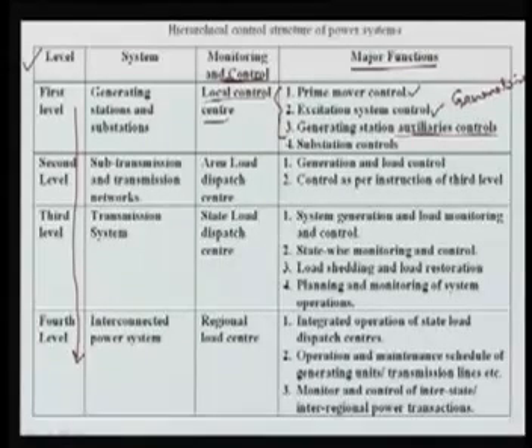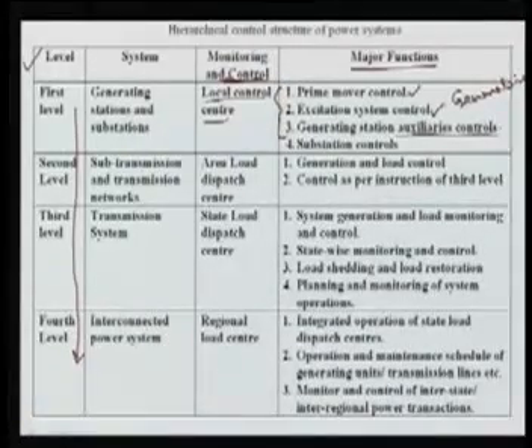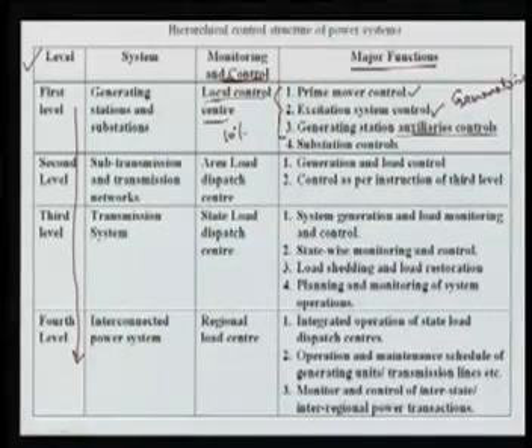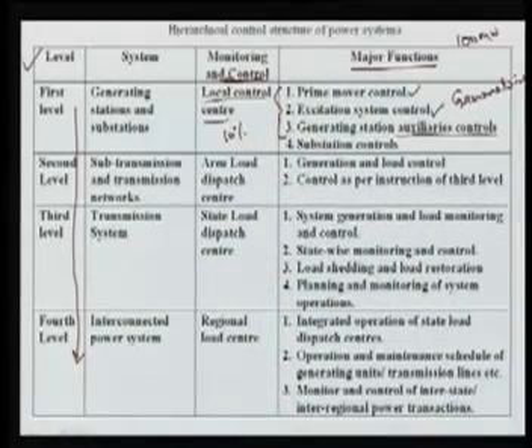Excitation control, as I said, is nothing but we have to set the voltage of the generating unit, the terminal voltage, so that we can generate the required amount of reactive power. And the other auxiliaries, the various auxiliaries used in the generating power station. I just want to tell you, in the thermal power station, 10% of the rating of a thermal unit is consumed for the auxiliaries itself. Means if you have a 100 megawatt unit, you require 10 megawatt of power, and that is consumed in the auxiliaries of that generator itself.